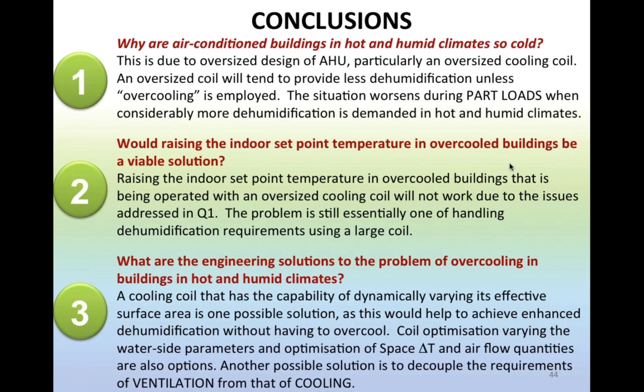So, thank you. Renier asked, does a higher supply air temperature and lower delta T not improve the coefficient of performance and offset the reheat and fan power increases? Is that something you can address? Well, I'm not sure I am with you on that reasoning, because to get to a higher supply air temperature, you would probably have to do an overcooling part. Otherwise, you can't get the right humidity level. And that was the point I was trying to make earlier.